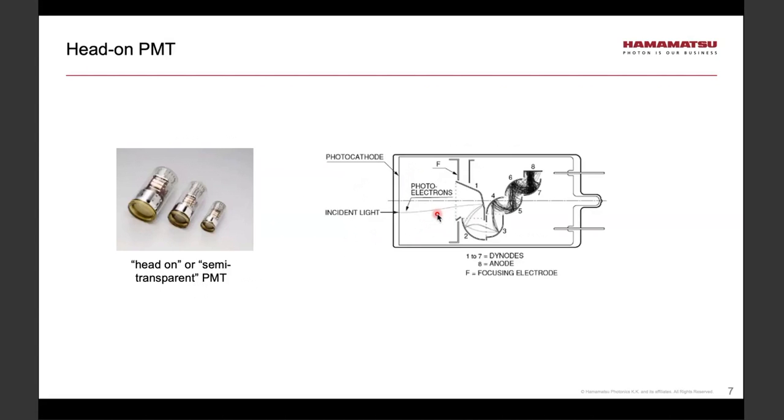Now, another common design is known as head-on PMT. Again, a portrait of such PMTs is on left-hand side, and on right-hand side, again, we have a computer simulation of the paths of electrons in this particular type of a PMT.